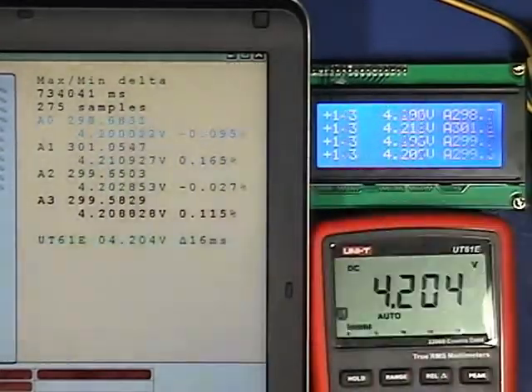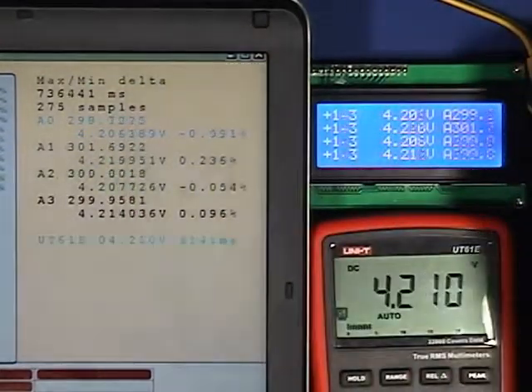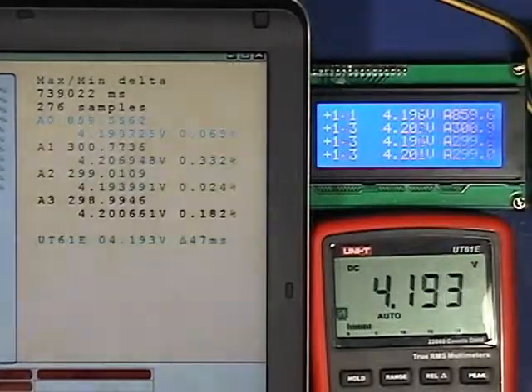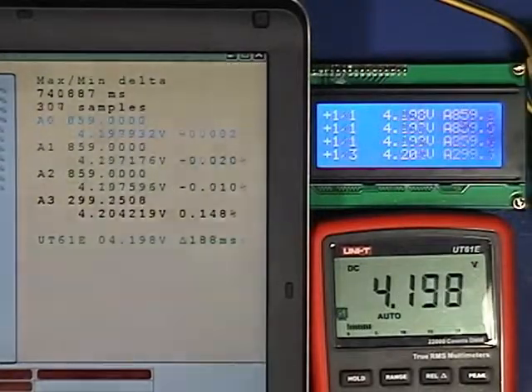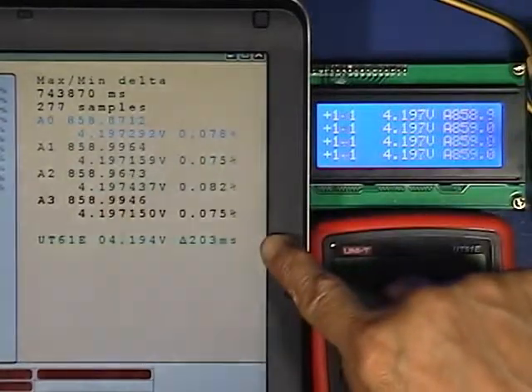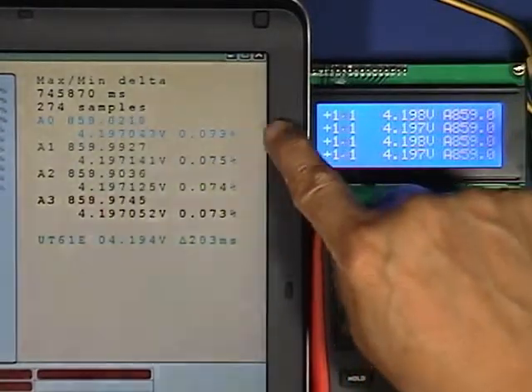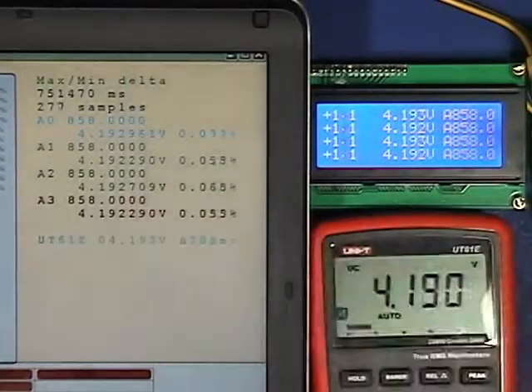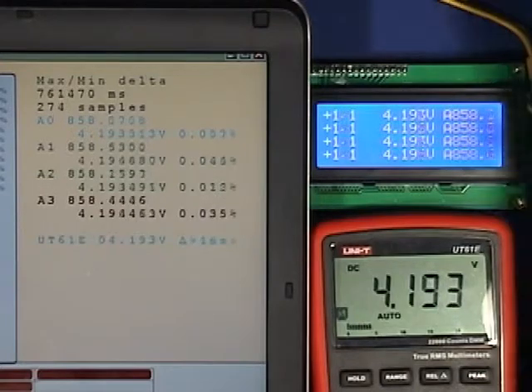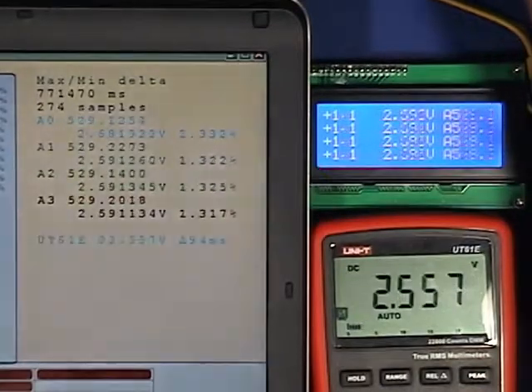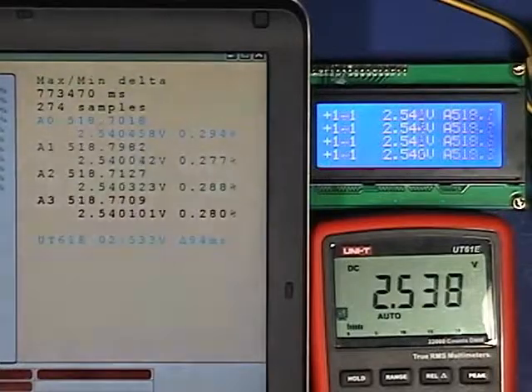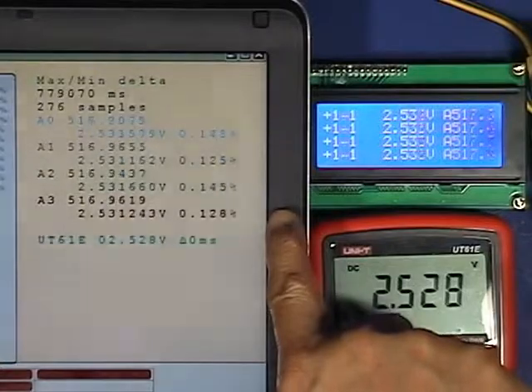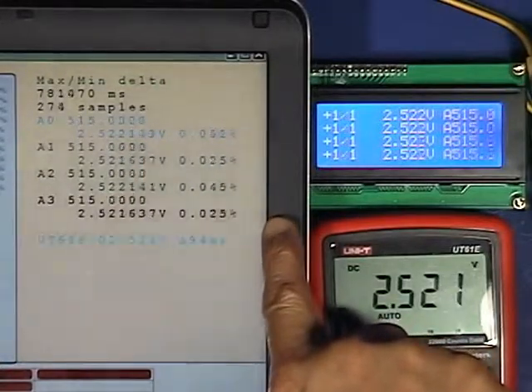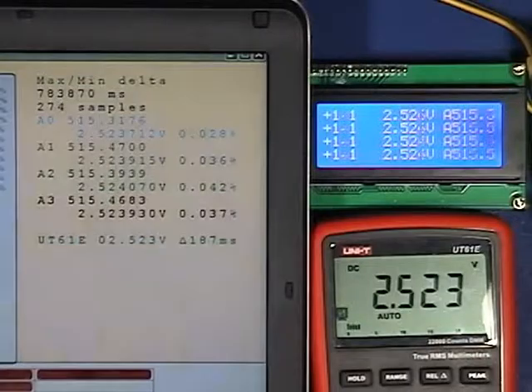While I'm still on the 15 volt range, I'm going to switch to the 5 volt range now. 5 volt range. The error is very good. 0.07% error. 0.09. Now it's closing in on the 2.5 volt range. Error rate is very respectable once it settles in. Again, 0.1, 0.0% error for all 4 channels.